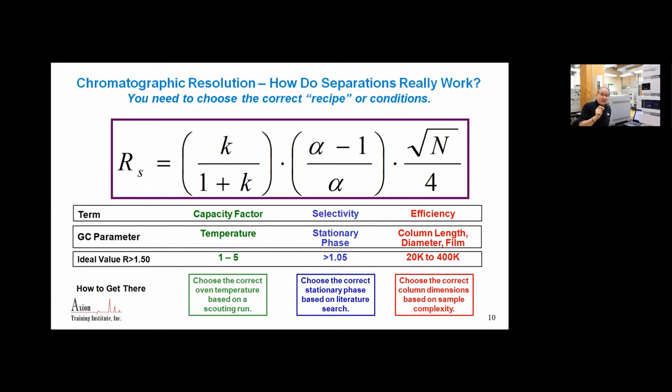This little k should be between one and five. If your k is less than one, your GC is too hot. Cool it down. Lower your column temperature. If your little k capacity factor is greater than five, you're wasting time. Heat that thing up. Get those peaks off the column. Capacity factor tells us, do we have the right temperature for the separation? It's like the Goldilocks thing, right? Not too cold, not too hot. We need it to be just right. Capacity factor tells us if we have the right temperature.